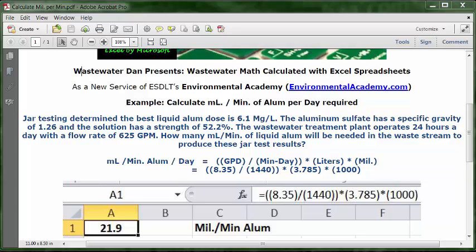Today's example: calculate milliliters per minute of alum. The problem reads: jar testing determined the best liquid alum dose is 6.1 mg/L. The aluminum sulfate has a specific gravity of 1.26 and the solution has a strength of 52.2%.